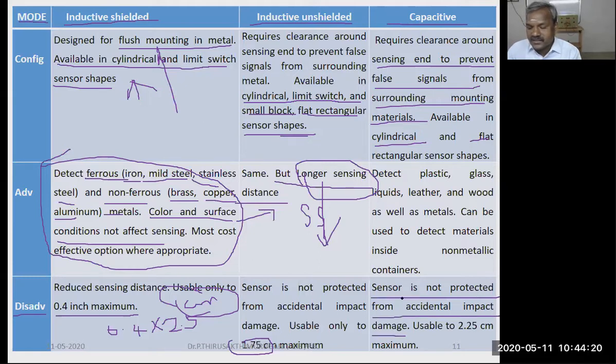The capacitive sensor is not protected from accidental impact damage. This is the disadvantage of the capacitive proximity pickup. It is also used for much longer distance detection of objects, up to 2.25 centimeters. So this is the comparison of the three types, a big 10-mark question consisting of inductive, capacitive and comparison. Understand or not? This is about the proximity sensor.